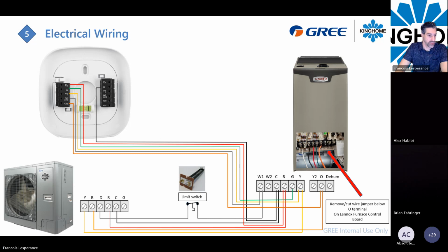Switch, when you are putting that, it should open at 100 °F. So what temperature should it close at? Well, depending on the switch, you can have a switch that closes at like 40 or 60 Fahrenheit and opens at 100 Fahrenheit. This switch will be normally closed in normal operation. Because you are in defrost, you will bring some cold air to the coil, so at a certain point it will close, and then your furnace will be on when the D signal activates the W1.